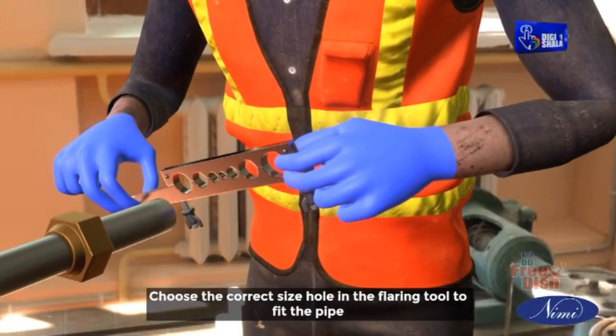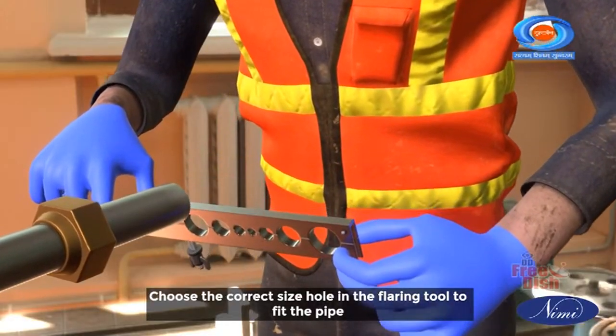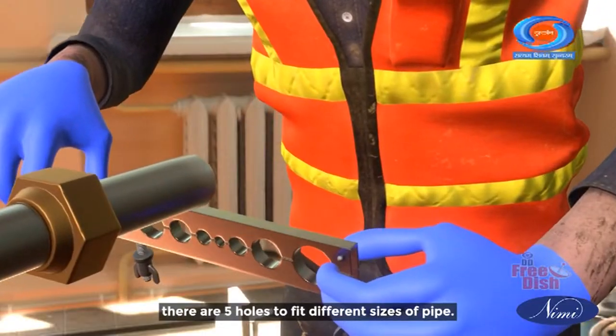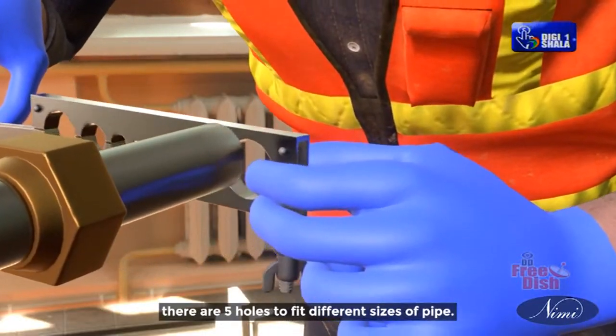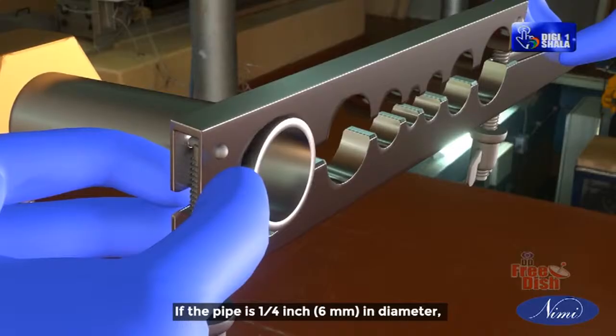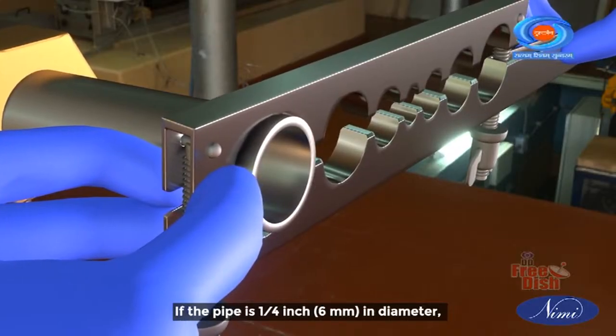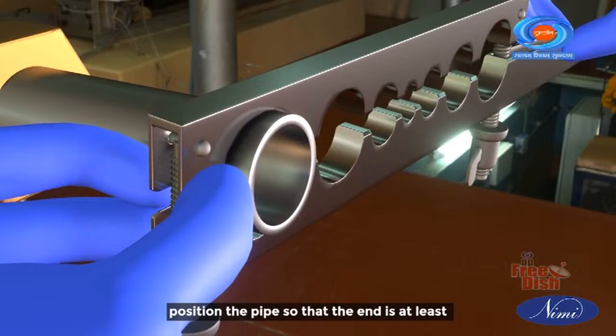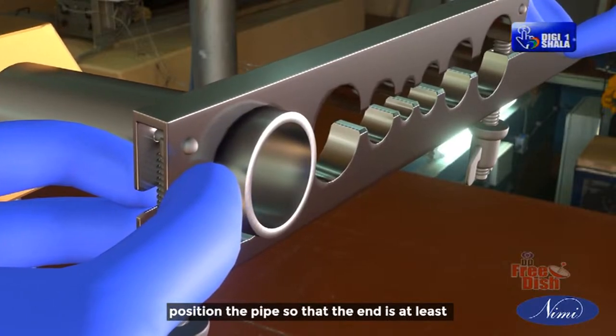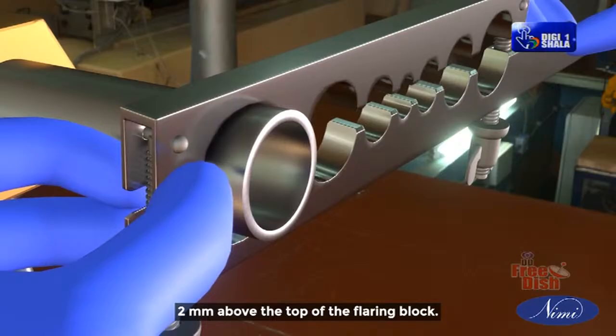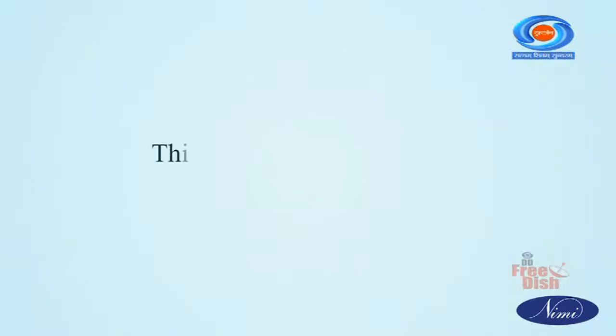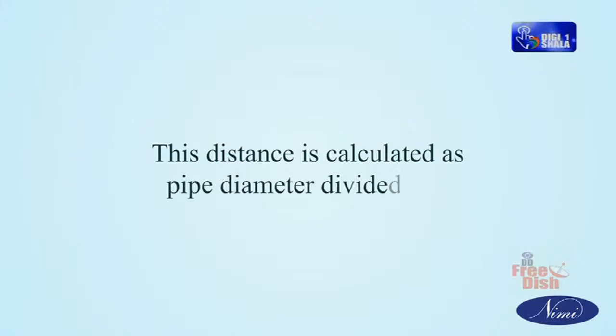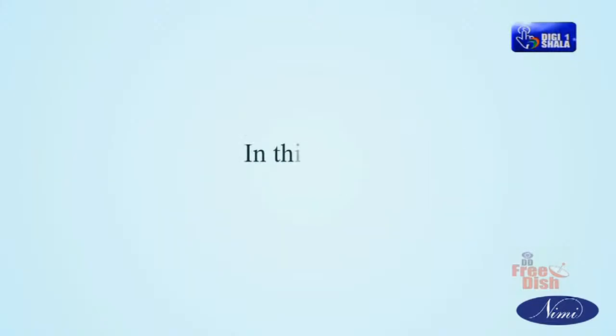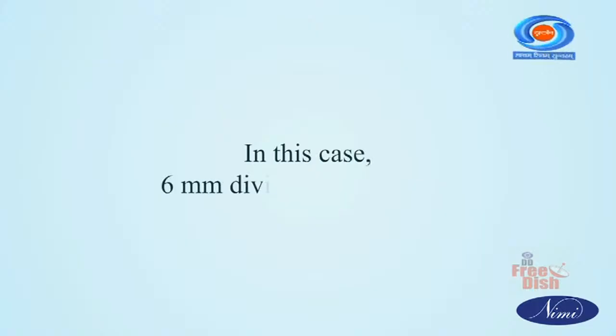Choose the correct size hole in the flaring tool to fit the pipe. There are 5 holes to fit different sizes of pipe. If the pipe is 1 by 4 inch, 6 mm in diameter, position the pipe so that the end is at least 2 mm above the top of the flaring block. This distance is calculated as pipe diameter divided by 3. In this case, 6 mm divided by 3 is equal to 2 mm.